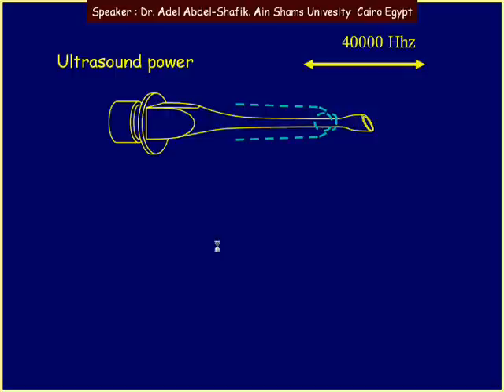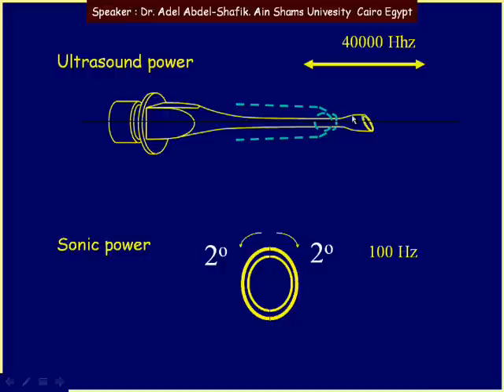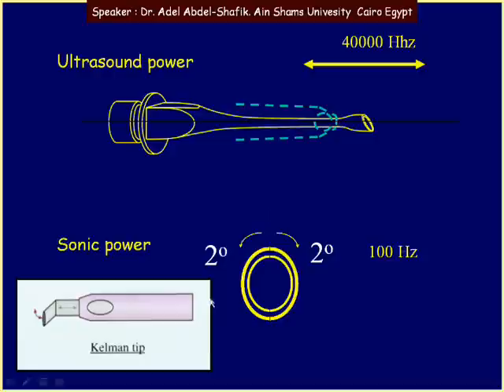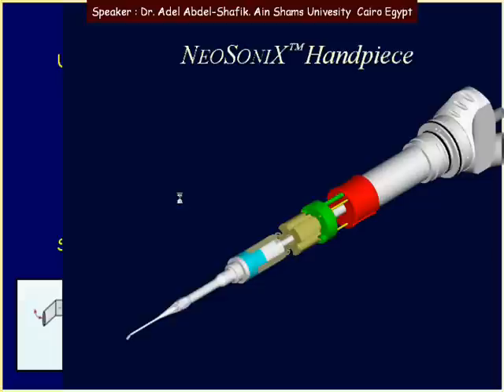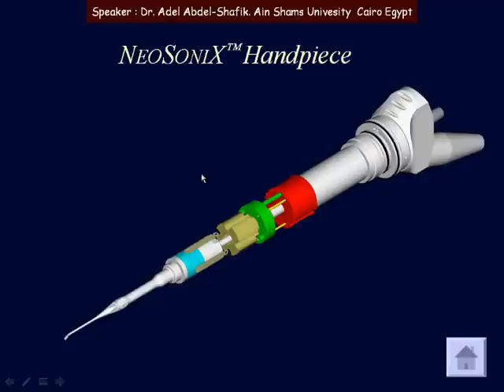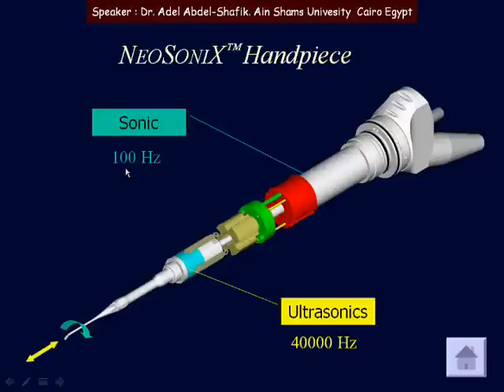More recently, some machines have added a rotatory movement along the axis of the needle — not only the regular forward and backward movement of the ultrasound. This rotatory movement can be half a degree to each side, one degree, or two degrees. If this is applied with a Kelman tip, you get a wider effect. This is seen in the NeoSoniX handpiece of Alcon, which combines regular ultrasound with a small rotatory side-to-side movement.